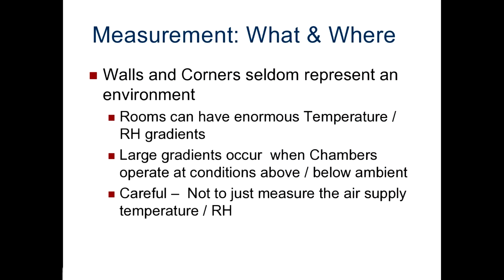And we also must be careful not to measure the airflow into a room or into a chamber. Those can be quite different than the conditions within the room or chamber itself. And again, if it was winter, for example, and quite cold, the air that's coming from the heating system will be quite warm. And if we're just measuring that, we may not get a good representation of the conditions within the room. And it's the same situation with a chamber.